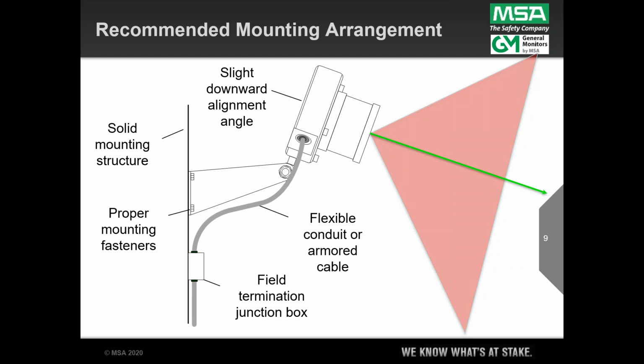And in fact, as part of the commissioning process, and I've done this where I've been given a site coverage map, and I've got to go out and align the detectors to match the map, and that means both left to right, the horizontal axis aiming, and then the vertical axis aiming. So again, we want a solid structure. We want a nice, I need flexible conduit. I was at a job site once where they had hard-walled the conduit into the device. It's like, guys, this is not going to allow us to align it.